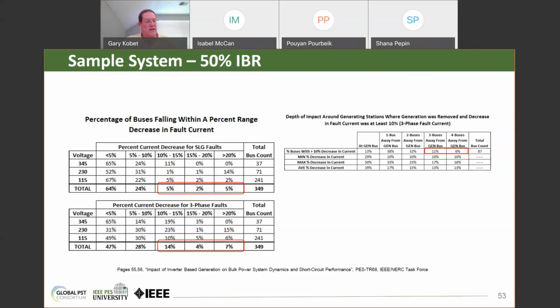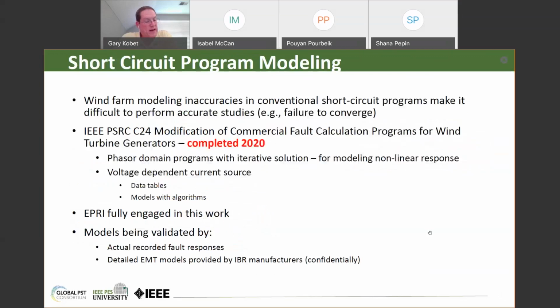The next slide talks about short circuit program modeling. EPRI, along with Power System Relay Committee Working Group C24, did a lot of work specifically on fault calculation, fault modeling, and wind farm modeling in commercial fault calculation programs. That work was completed last year, and their report is available on the PSRC website. What they do is come up with a voltage-dependent current source model that can be used with either a table or models with different algorithms based on the control method. So that report is available.